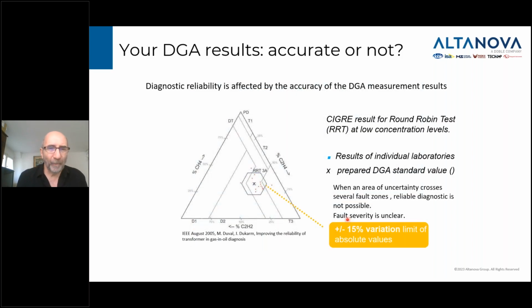Now, why is accuracy important in diagnostics? Here's an example. We took the Duval triangle, which is widely used around the world. You can see here, with the X, the exact measurement of whatever gas sample we had, with zero error. So if there was 100 ppm in that sample, it measured 100 ppm of all the gases. And we put the results into the Duval triangle.